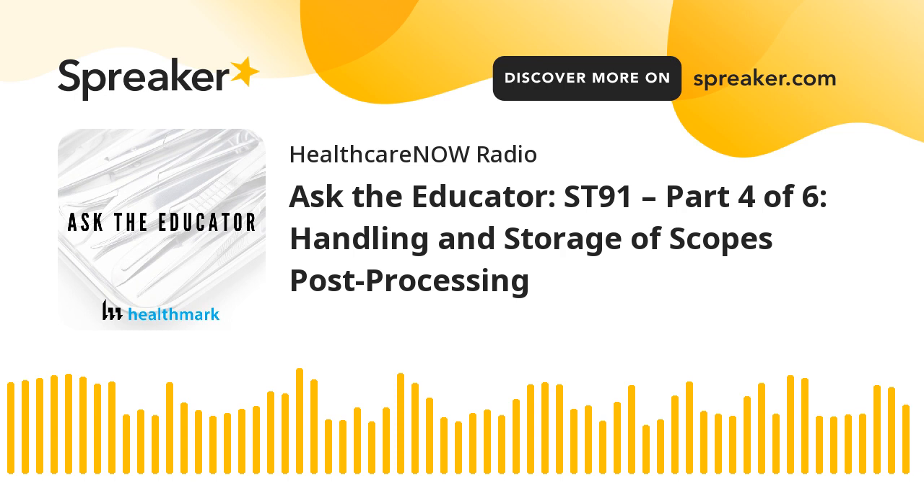When the standard says something is preferred, it means if you're in the market for a new cabinet anyway, here's what the standard says is preferred—try to go for this if you can, because this has shown better results than the alternatives. But if you have an existing cabinet that's compliant and has HEPA filtered air and does all the things minimally that we want, then you're fine with that, because that's the minimum standard. The best cabinet I've ever seen was a wooden cabinet built in someone's garage—they knew there was an air filtration requirement, so they drilled holes in the side.